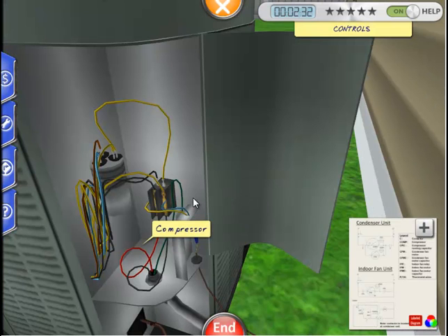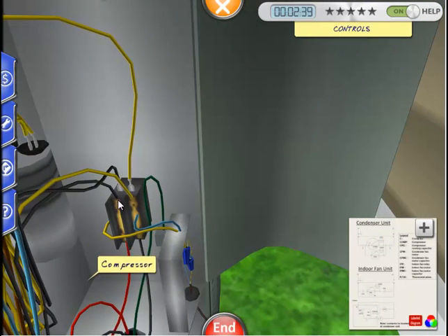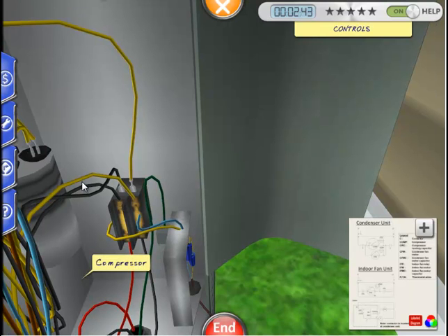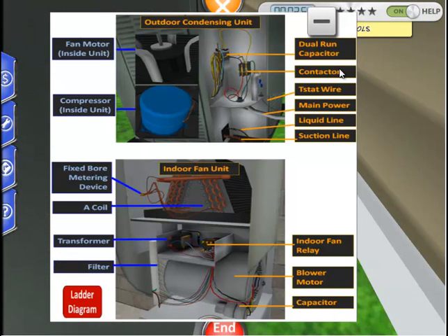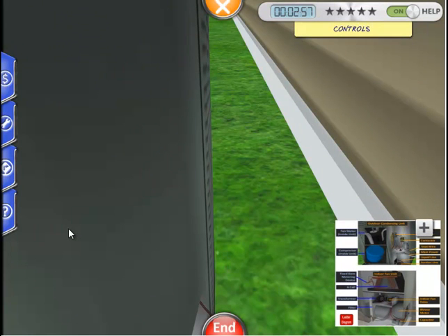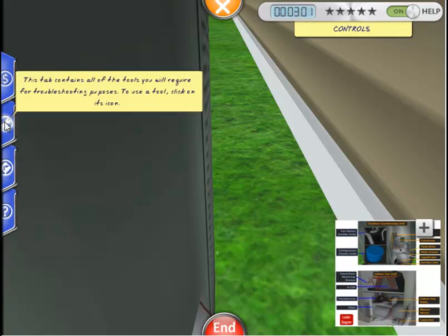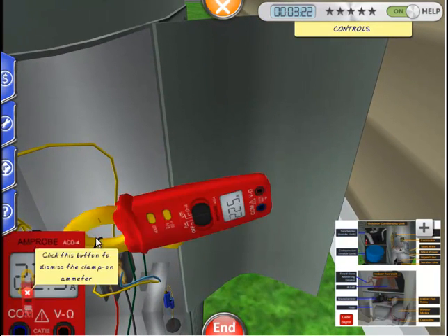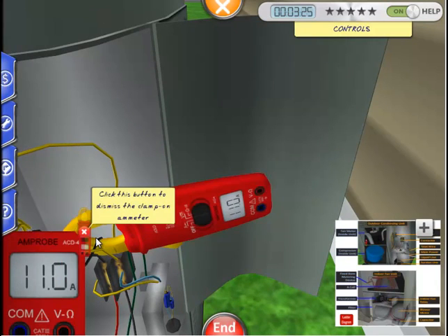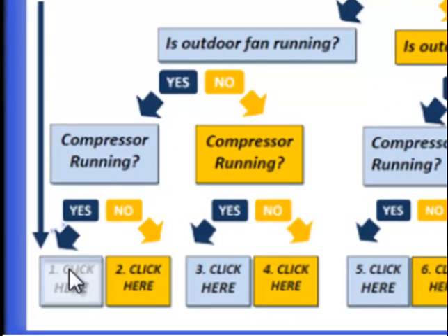With one right click, you can recenter your frame of reference to get a more accurate or detailed view. Let's zoom in on the compressor wire, which is the black wire located on the back left of the contactor. The wiring diagram, especially the color version, and the labeled diagram are helpful in identifying key parts of the air conditioning system. Let's click on the tool tab and select the clamp-on ammeter. Let's place it on the compressor wire, which has a helpful glowing hot spot for placement. A reading of 11 amps confirms that this is the compressor and that it is operating. The outdoor fan motor would only have a reading of one or two amps. Since we know all three loads are running, we can conclude that the problem is mechanical and follow the steps in scenario one.